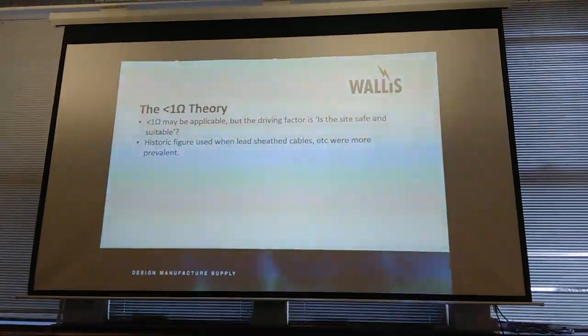Yeah, it sort of comes from the fact that historically, with lead sheath cables in the centre of Birmingham, the centre of Nottingham, the centre of Leicester, all these big cities, all of the distribution network was connected together with these conductive sheath cables. So you had this wonderful global earthing system. You only needed to really get a reasonable figure at your substation, because you knew full well that all of the fault level was going to go up the cable sheaths into the general mass of Earth that way.